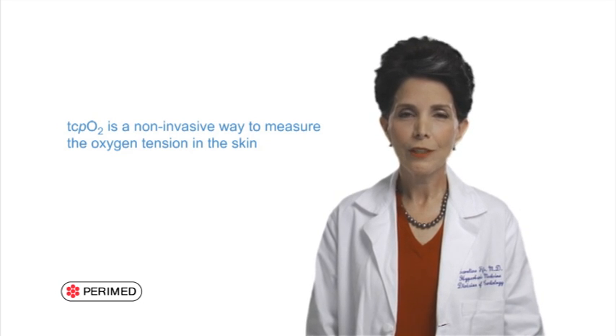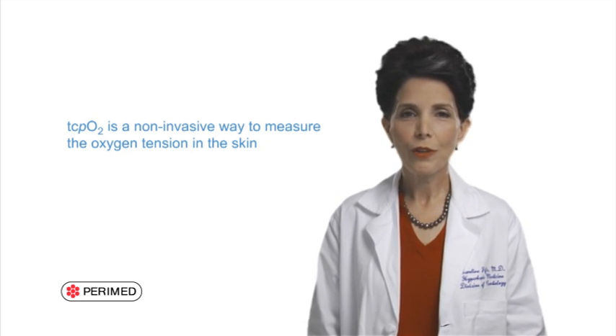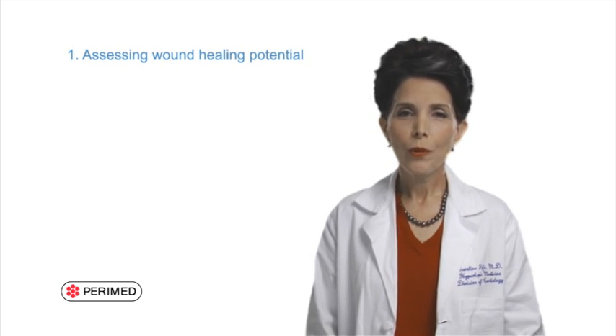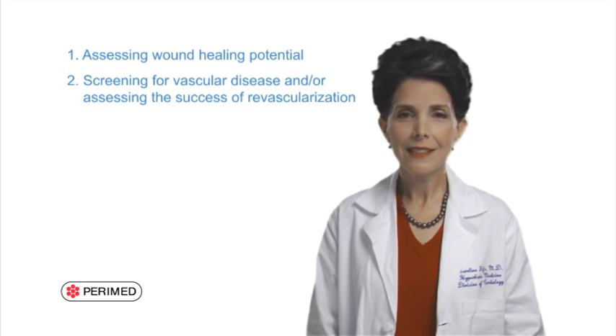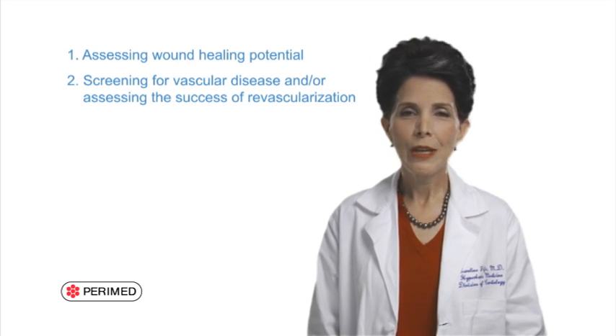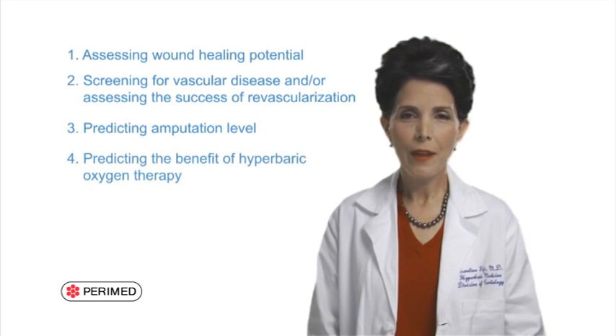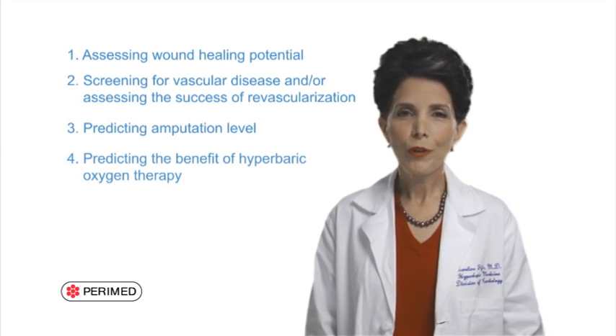Transcutaneous oximetry is a non-invasive way to measure the oxygen tension, that is, the partial pressure of oxygen in the skin. The four applications of TCPO2 we will discuss in this video are: assessing the wound healing potential, screening for vascular disease and/or assessing the success of revascularization, predicting amputation level, and predicting the benefit of hyperbaric oxygen therapy. I will refer to evidence-based interpretation guidelines developed by an expert panel and published in the Journal of Undersea and Hyperbaric Medicine.